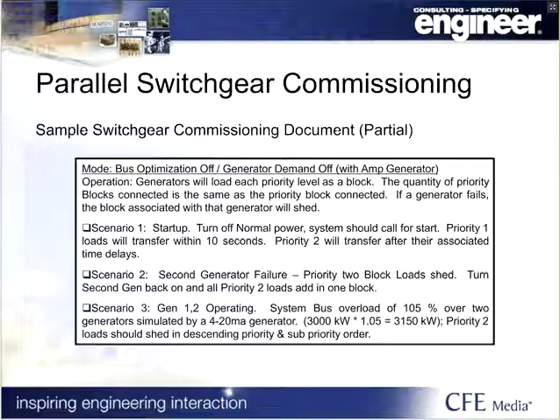Depending on the programming of different manufacturers, they all do it slightly different. There's some common ground, but there are certainly drastic differences between the manufacturers. They would respond. Like if the 2nd generator comes off, I might shed the 2nd tier of loads. Just for an example, this is a 2-generator system that I'm showing you here. The 3rd scenario, which I tested, was, let's say I have 105% of my loads over 2 generators, but I have 2 generators running. What does it do? It should start cutting loads off, because it is going to inherently protect the system. I mean, that's the final goal, to protect the priority 1 loads and make sure the life safety loads stay on.